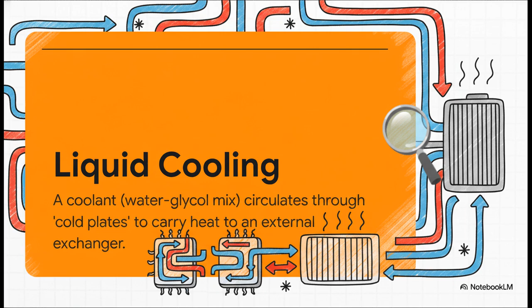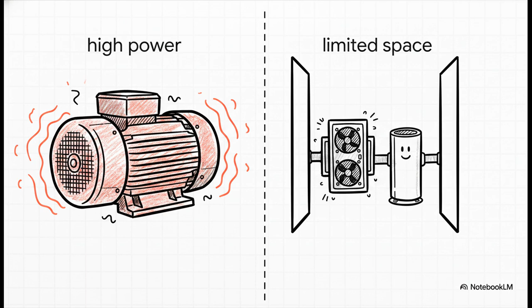There's a special coolant, usually a water glycol mix, that gets pumped through sealed plates bolted right onto the hottest parts. The liquid soaks up the heat and carries it far away to be dealt with somewhere else. So when do you use this? It's the go-to solution for the really big jobs, we're talking drives over 500 kilowatts, or in situations where you physically just can't fit a giant air-cooled cabinet.